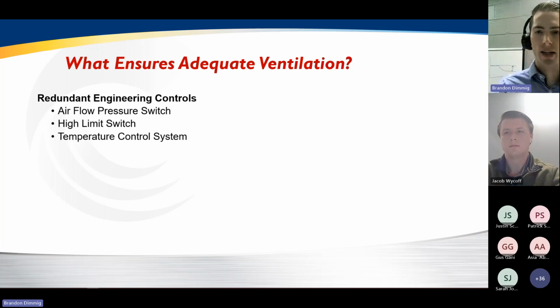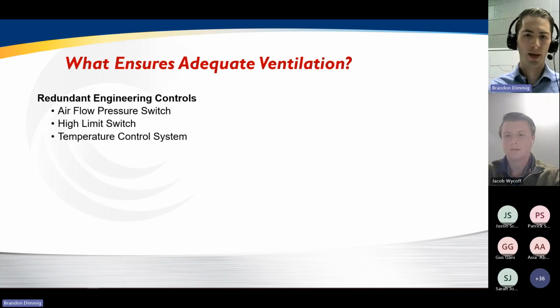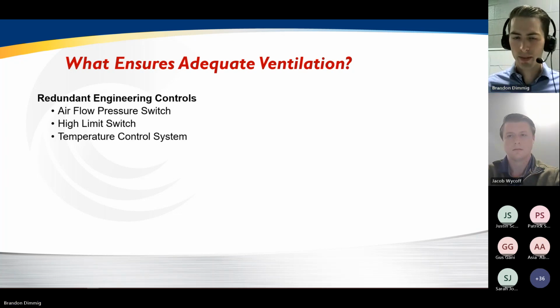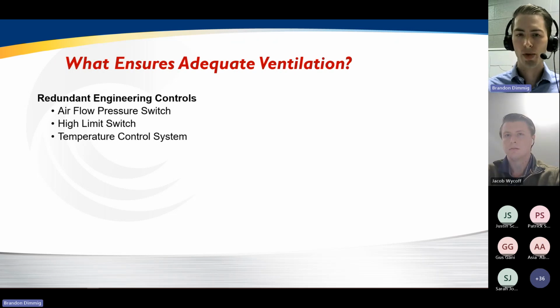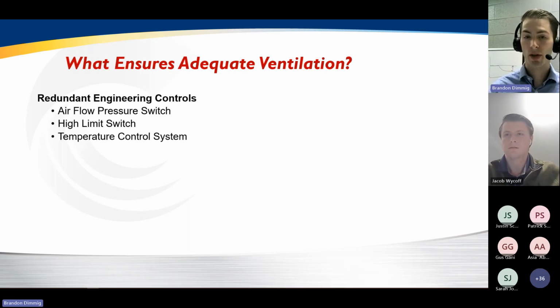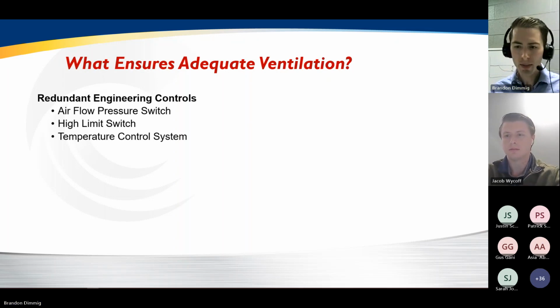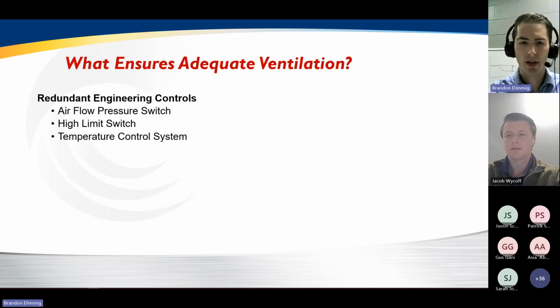So how do we make sure that we've got consistent and adequate ventilation, that we're not building up harmful combustion byproducts in the space? There are a number of electrical controls designed into the unit that prevent this. The first is an airflow pressure switch. And really, all the switch does is make sure that there is at least the minimum required airflow across the burner to ensure proper combustion. If the airflow falls too low, the unit will shut down. There's also a high temperature limit switch on the discharge temperature, preventing excess temperatures from discharging into the space. So if the discharge temperature gets above the limit, again, the unit will shut down in case there's an unsafe condition. And then the third is the temperature control system, which modulates the gas input into the burner to again ensure that the discharge temperature is within an allowable range.